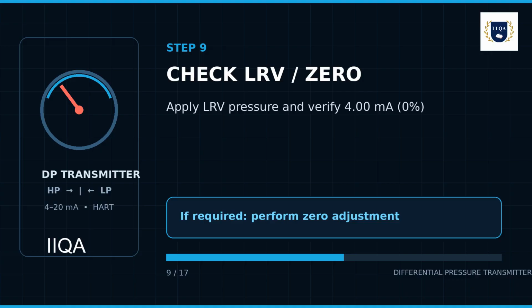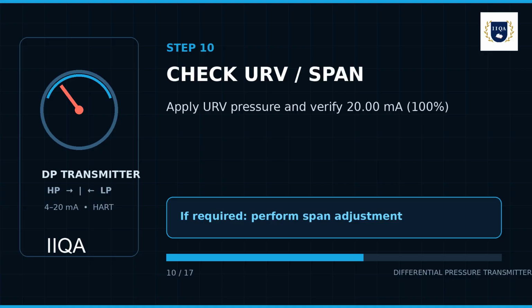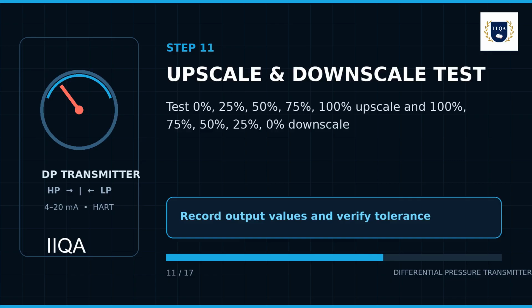11. Apply test pressures at 0%, 25%, 50%, 75%, and 100% of the calibrated range during the upscale test, and 100%, 75%, 50%, 25%, and 0% during the downscale test. Record the corresponding output values and verify that they are within the acceptable tolerance.